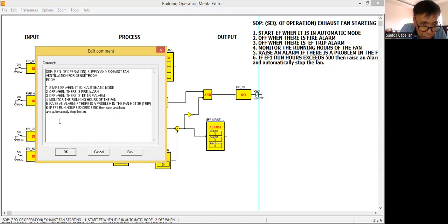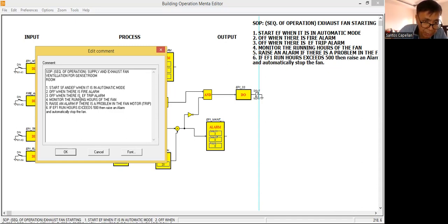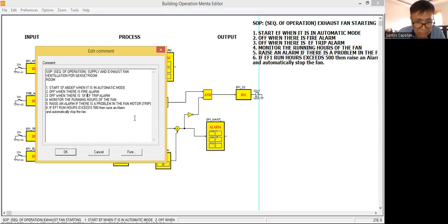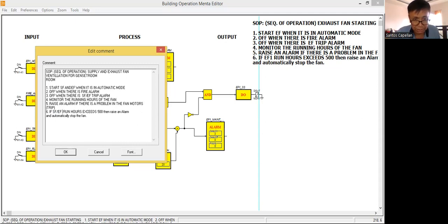So the sequence of operation: start EF, then I will add also start SF when it is in auto mode. Then if there is a fire alarm, stop SF and EF. Monitor the running hours and raise an alarm if there is a problem in the fan motors — EF1, SF, and EF run hours. Then raise an alarm and automatically stop the fans.